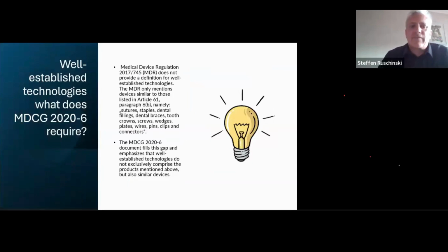So what is a well-established device according to the MDCG 2020-6? Medical Device Regulation 2017/745 does not provide a definition what a well-established technology is. The MDR only mentions devices similar to those listed in Article 61, paragraph 6b, what are namely sutures, staples, dental fillings, dental braces, tooth crowns, screws, wedges, plates, wires, pins, clips, and connectors.